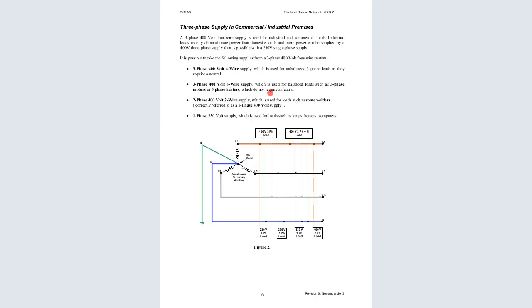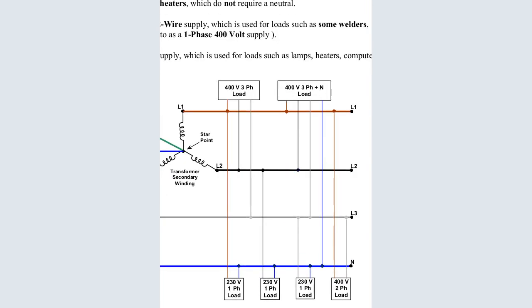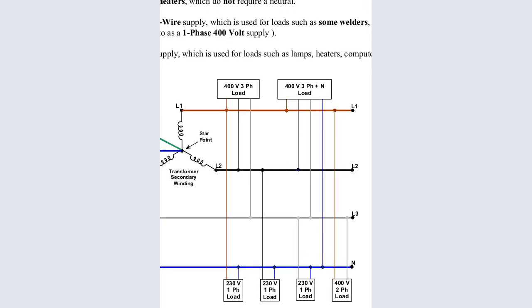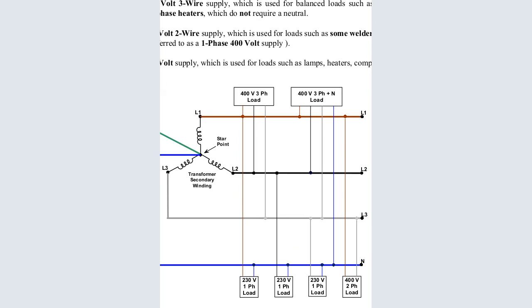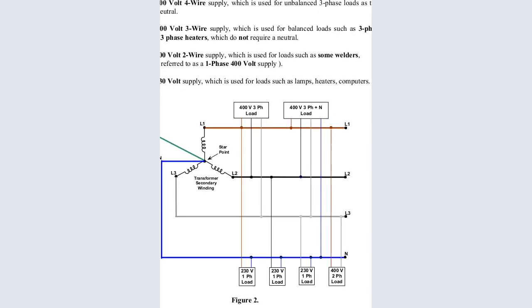And then we have another load that can be supplied without a neutral. So this is an example of a load that is tapping without a neutral. The kinds of loads can be the ones that are used for heaters, things like motors, 3-phase motors. So this is an example of that load. It is just tapping the lives. So you can see this one is tapping just 3-phase from this line. The second live phase is from line 2. It is tapping it from this point. And then the third phase, it is tapping from this point to the load. So you see this load is not getting the neutral. So it just gets the 3 phases.